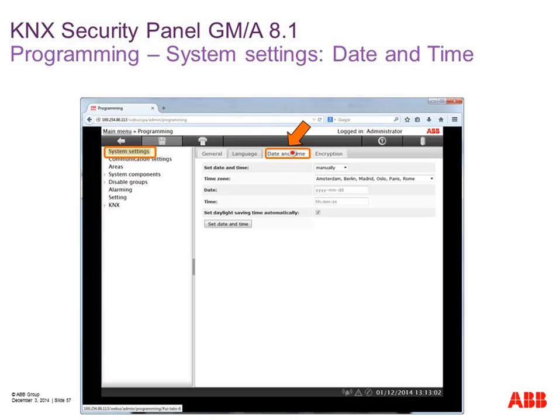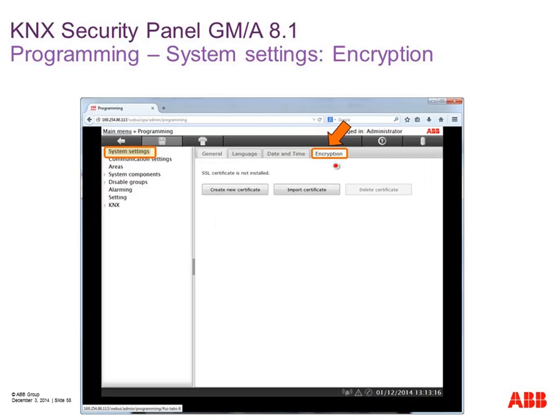Via the 'time and date' menu we can set the time and date of the intrusion alarm panel manually or automatically, and also send this time and date to KNX. Via the 'encryption' button we can import or create our own SSL certificates. As a default we communicate via port 80 using standard browser functionality, but for a higher level of security on the IP network we can create our own certificates and use SSL communication — like for online banking.